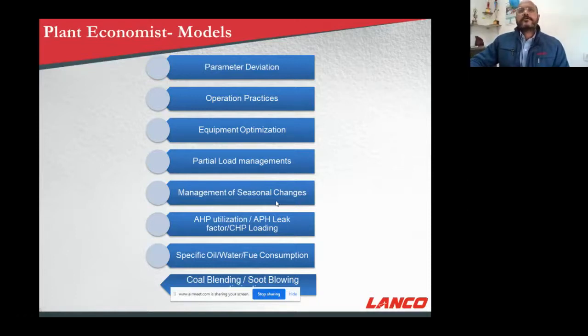Based power plants, part load operation is happening and certain optimization strategy operation has to be made. Whether we are doing it in the best way achieved or not can be put into the model to see the impact from the aux power or heat rate point of view. The management of seasonal changes we can also do. Then there are ash handling plant utilization factor, APH leak factor, coal loading. All these aspects are captured into the CHP loading, captured into the model. And then they are converted into gains with respect to aux power and heat rate, and can be further calculated into financial impact assessment.